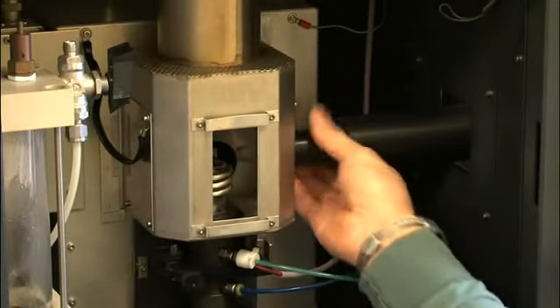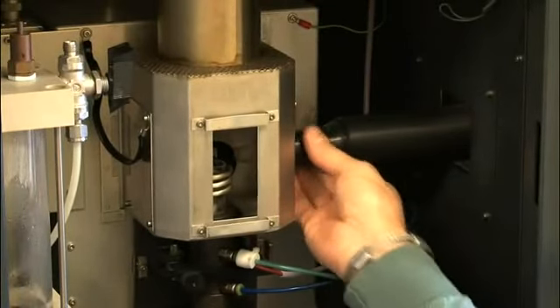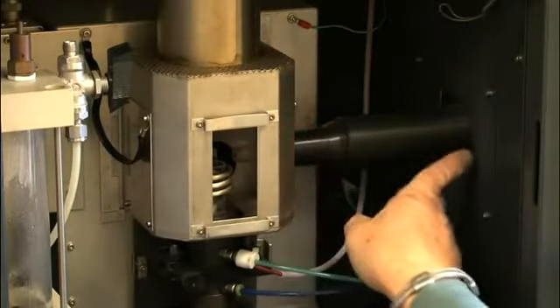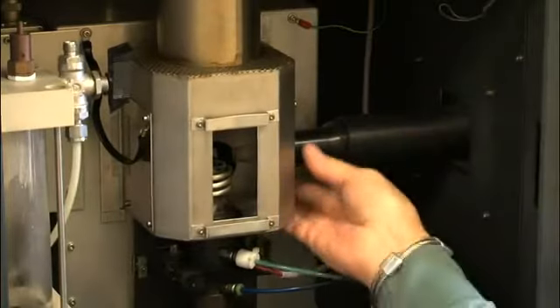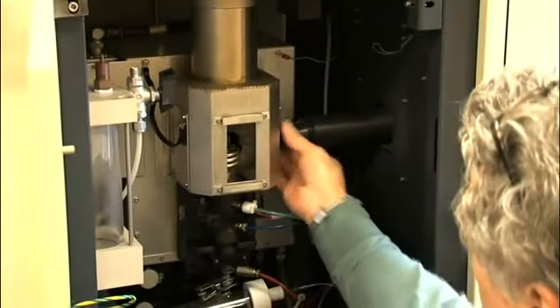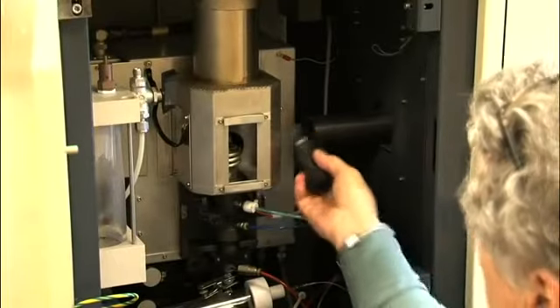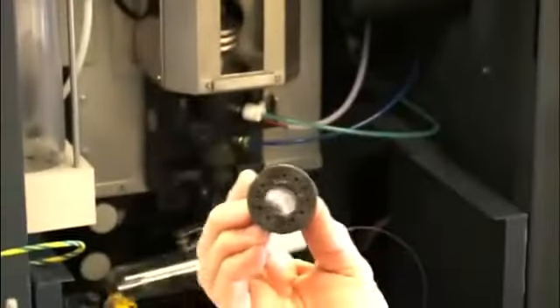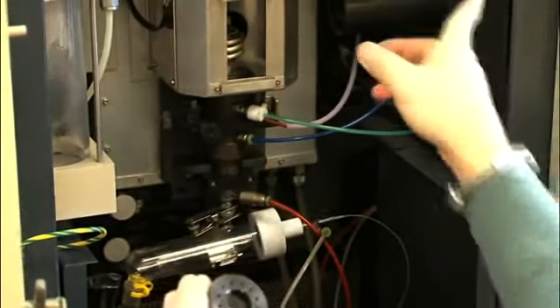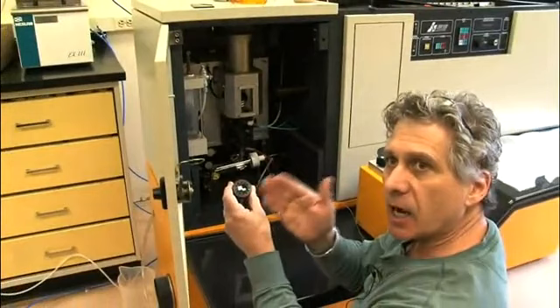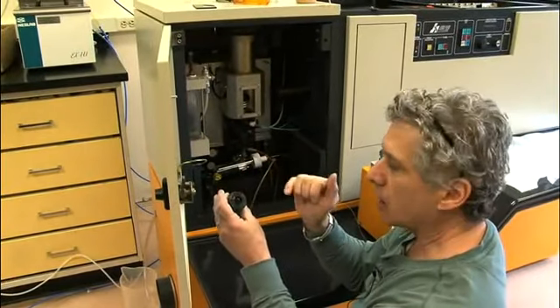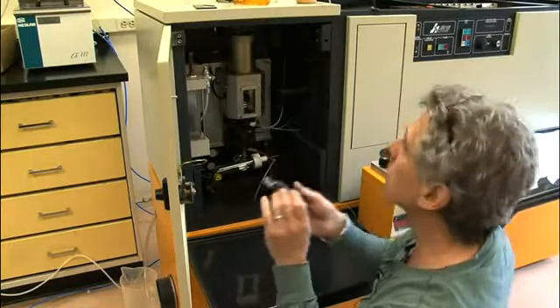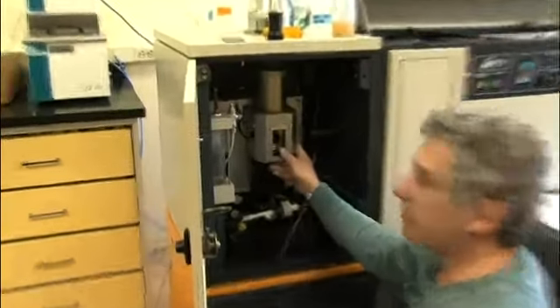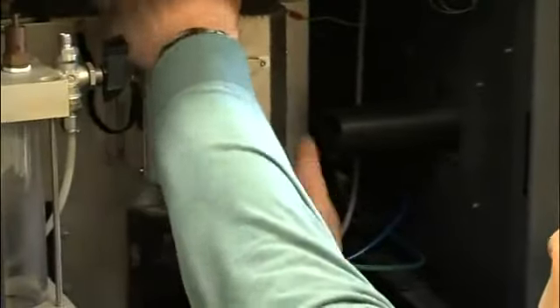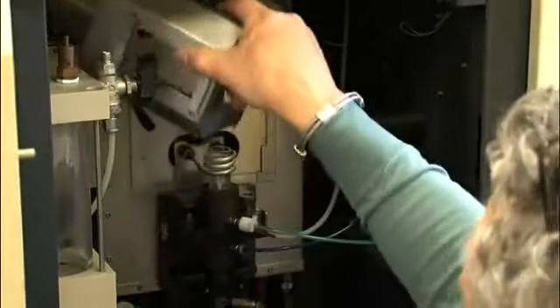There are 2 lenses in the optical channel. One is in this first part that I'm taking out. The other one is in the section that this tube connects to on the inside. So there's one lens right there. This just unscrews. The other one is the same way. They have a flat side and a convex side. They're cleaned with acetone only and a Kim wipe. I cleaned them yesterday. Then the Faraday cage will slide up to these notches, and then you could just take it off like this and just rest it up here.